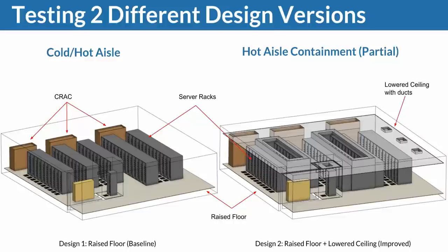The second hot aisle looks very similar to the first one, although if you have a careful look at the server racks that are closest to us, you will notice that they are empty. Let me try to get my spotlight tool. I hope that you can see the spotlight. We have empty racks at the very front, which is making a semi-opening to the hot aisle and will allow some kind of air recirculation.